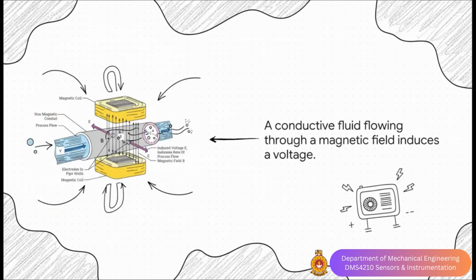Here's the physics, and it is just elegant. It's all based on Faraday's law. The coils create a magnetic field across the pipe. Now, as a conductive fluid, and this is critical, it has to be something like water, flows through that field, the fluid itself acts like a wire moving through a generator. This induces its own tiny voltage. The electrodes pick up this voltage, and the faster the flow, the higher the voltage. It's incredibly accurate, and there are no moving parts to wear out.